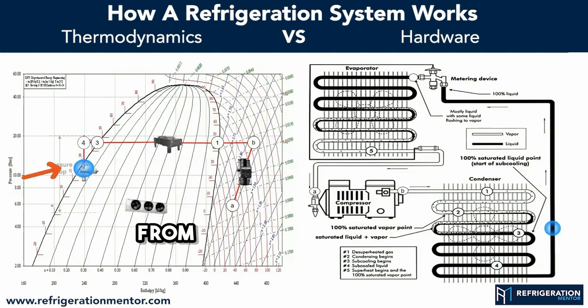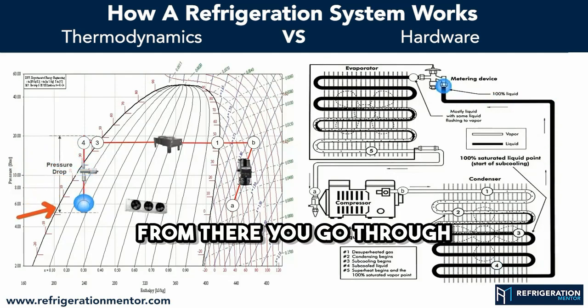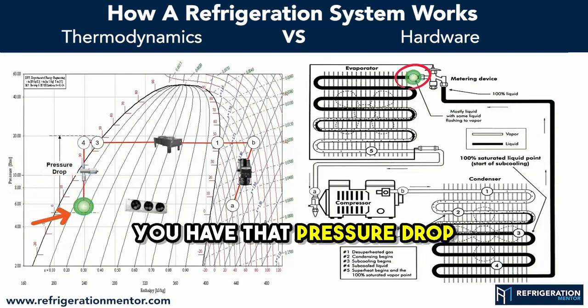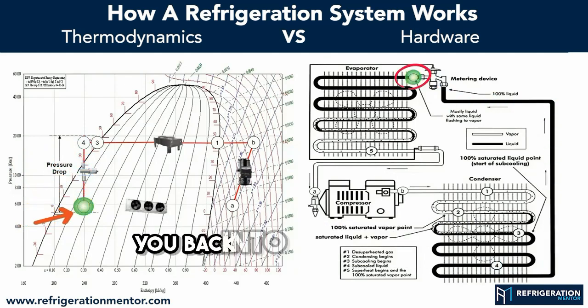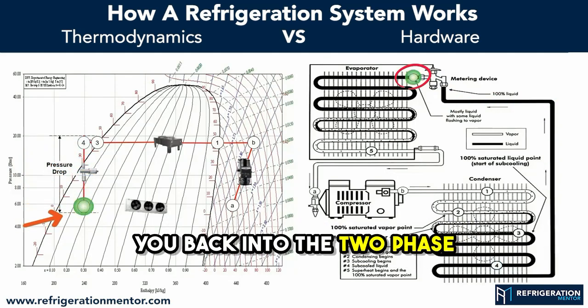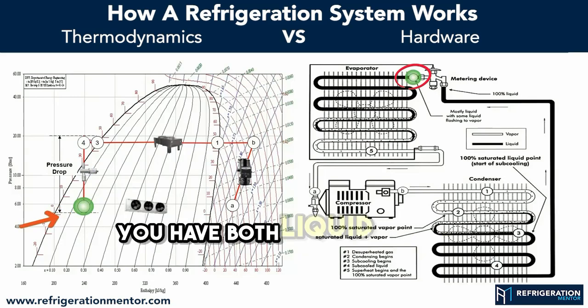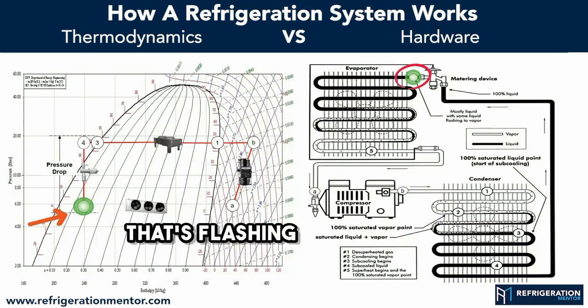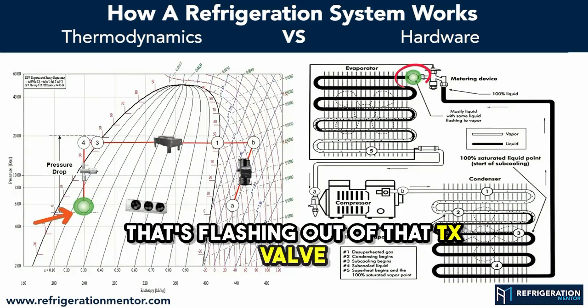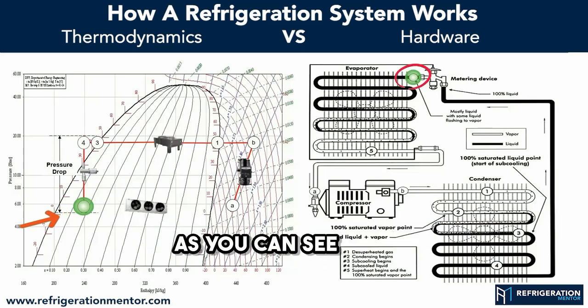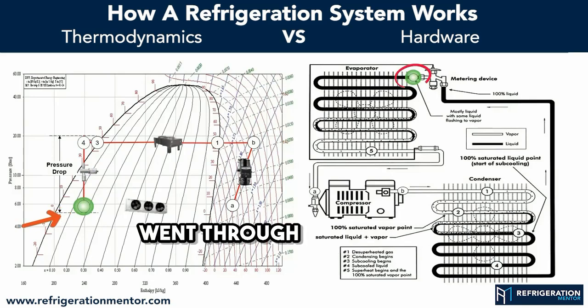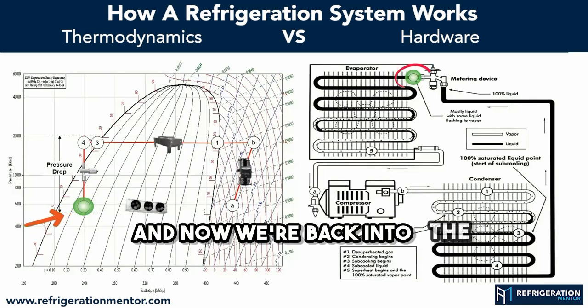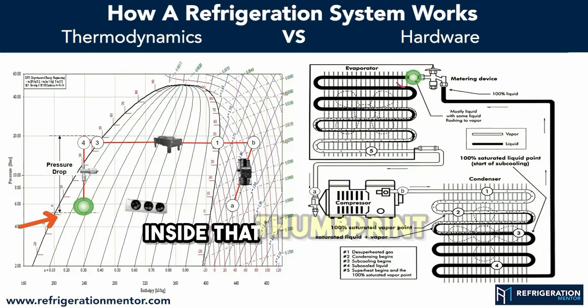From there, you go through your metering device. You have that pressure drop, which pulls you back into the two-phase. You have both liquid and vapor, and it's flashing out of that TX valve. As you can see, it just went through the metering device and now we're back into the two-phase inside that thumbprint.